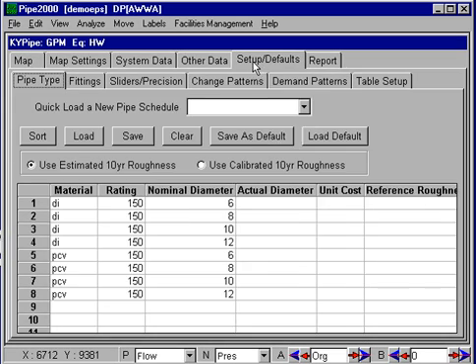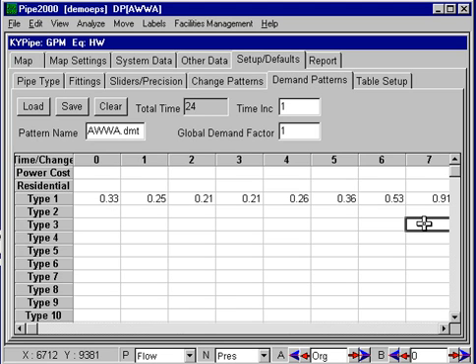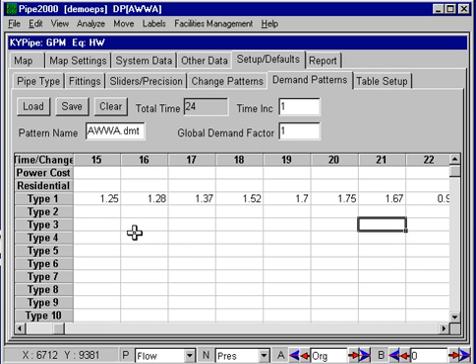This is done under Setups and Defaults, Demand Patterns. We can see that at time zero, which is like midnight or 1am, it's only 33% of normal demand, and this will increase as we go through the day up to some maximum values in the late evening hours of 1.75. This pattern is pretty much the one suggested by the American Water Works for residential systems.